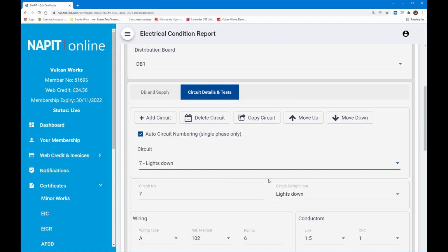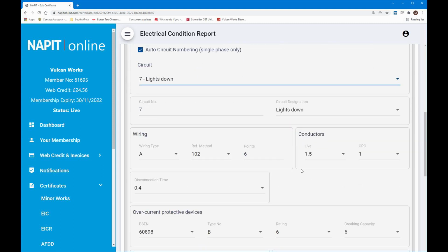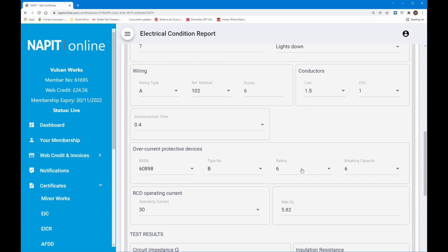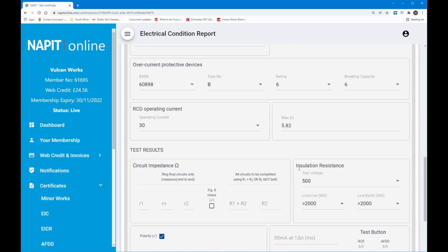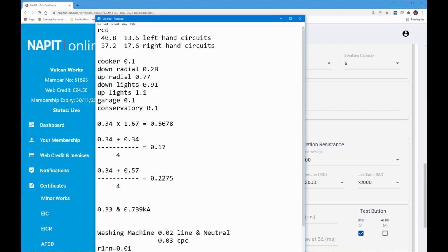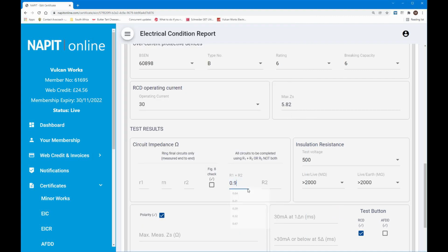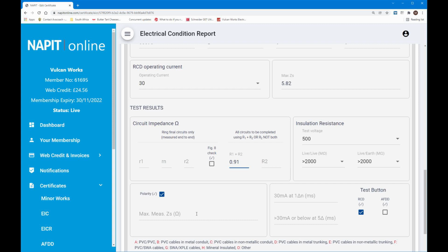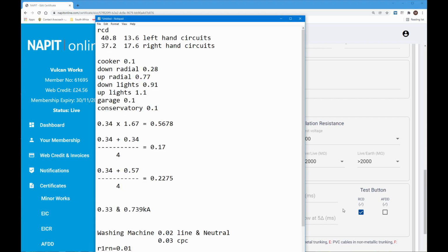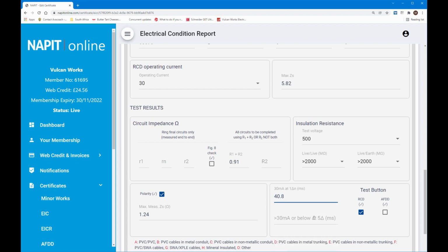And the downstairs lights. There are 6 downstairs lights, wired in 1.5 and 1, 6 amp rating, a maximum ZS of 5.82, and the reading I got for the downstairs lights I've lost it, 0.91. Again, I was able to do the insulation resistance on the downstairs lights, and here that's 0.33 added to that, which is for 1.24. Again, happy with that. And finally the RCD results, 40.8 and 13.6.